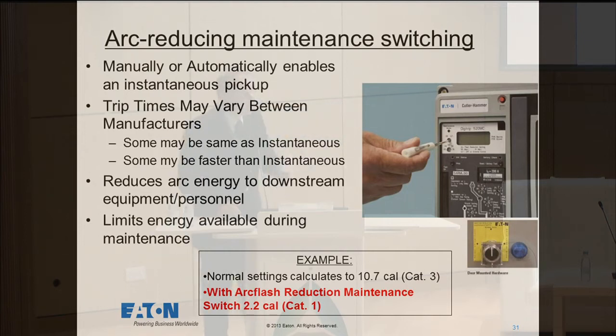The breaker knows that if anything happens when a worker's in there, you want that to go off as quickly as possible to limit the amount of energy that happens. You want to prevent damage to the equipment, you want to minimize damage to the equipment, and you want to prevent the employee from being hurt. So in this case, with a normal setting, it's a 10 calorie, and we bring it down to a 2.2 calorie, which is very simple clothing. So another technology advancement in many of the UL listed breakers that are on the market today.